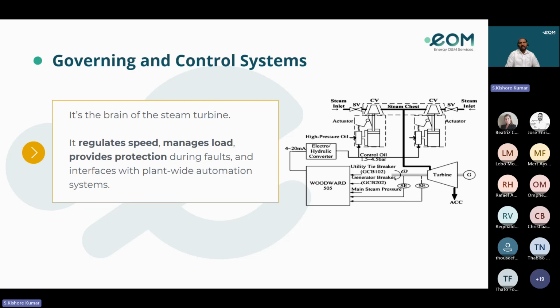Here we can see the speed sensor signal that feeds to the Woodward governor from the turbine. The signal from the Woodward governor feeds to the hydraulic converter, and the 4 to 20 milliamps goes there. Here it is converted to 1.5 to 4.5 secondary oil pressure, or control oil pressure. Based on that, the CV position and the steam flow will vary.